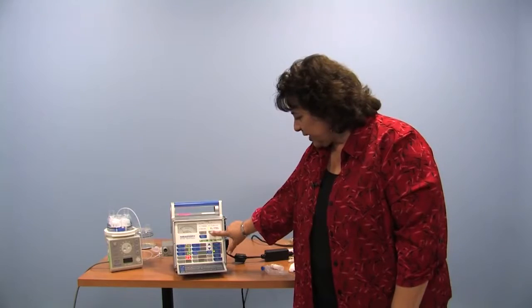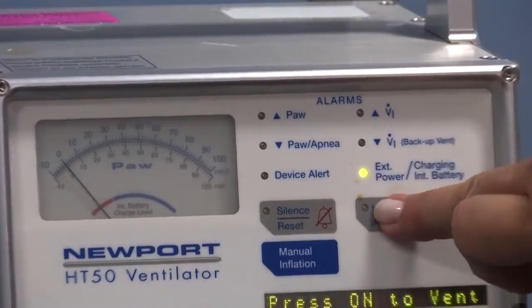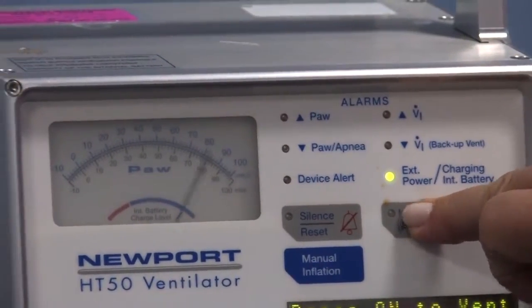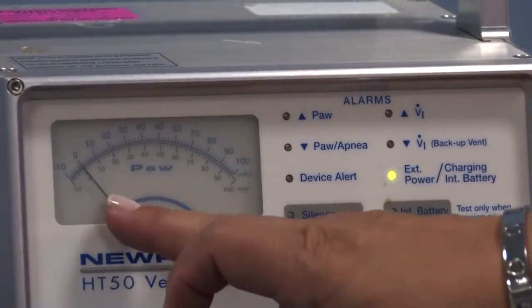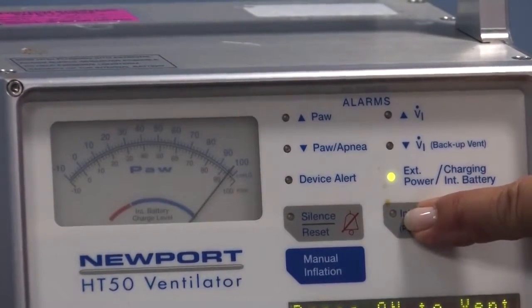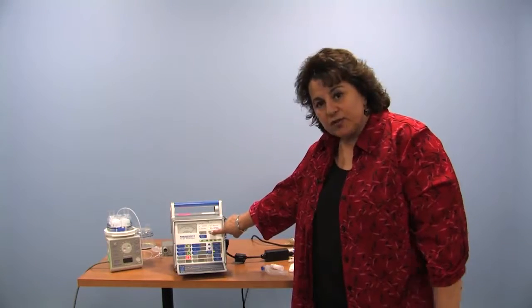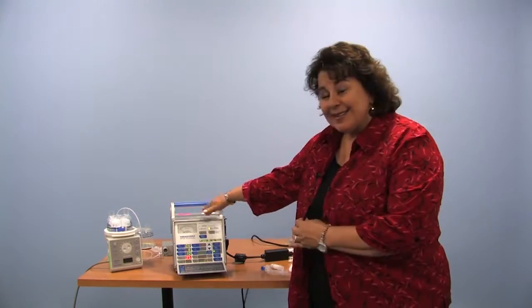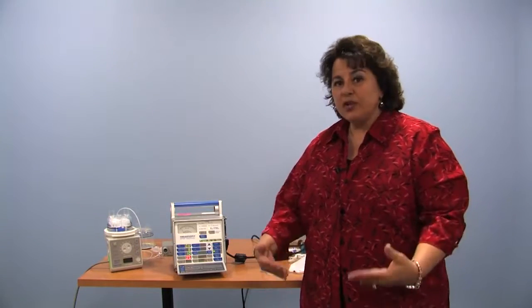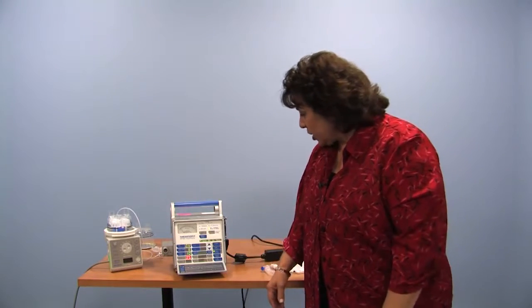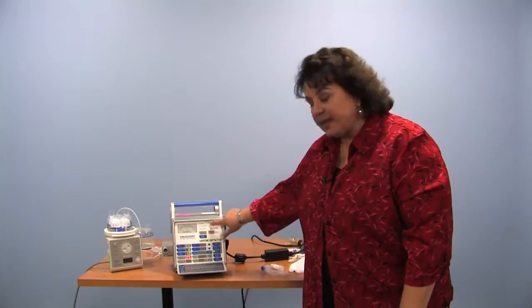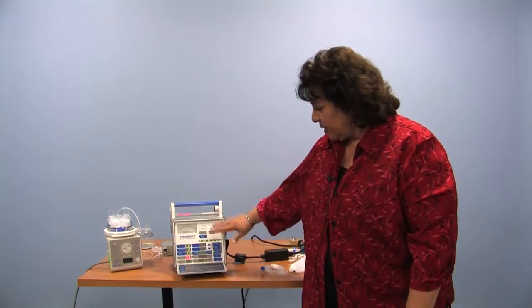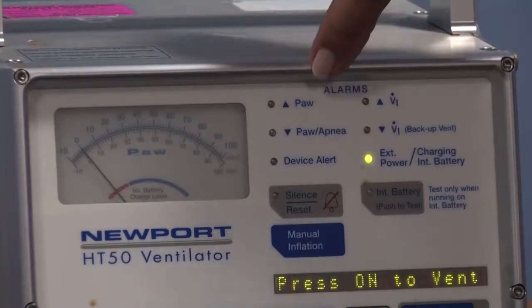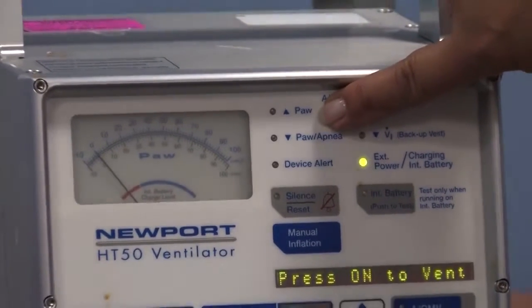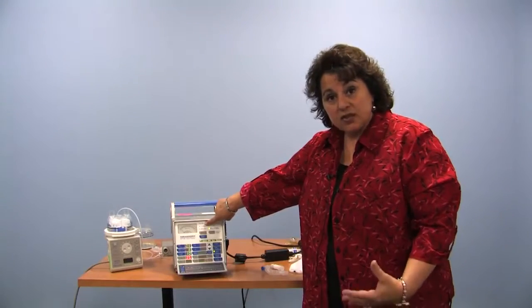Here it tells you that you can check the internal battery. If I push the button, it's showing me that my battery down here, you can't read it probably, but it's full. It says internal battery charge level, red up to blue. So this is a fully charged battery within the machine. Doesn't necessarily mean it's going to be 10 hours, which is why you should check that at home as well, because it may have lost its ability to take a charge. Up here you'll see lights for alarms with different symbols. If the high pressure goes off, the high PAW, high pressure light, will illuminate and stay illuminated until you reset it.